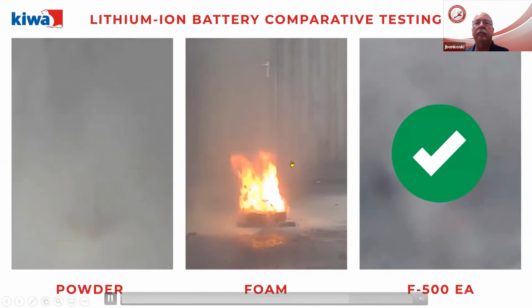These tests were done by Kiwa Labs on behalf of HCT Europe and Johnson Controls in trying to find an independent third-party solution for one of their clients. They had asked F500 to participate in the testing, and we agreed as long as they shared the results. So this is why you see Johnson Controls' name on this particular slide, because this comes right out of their literature where they're showing, based on the tests they did over the course of days, that powders were poor, not recommended, do not apply. Look at foam - well, Johnson Controls is a major foam manufacturer, so they really don't want to bash themselves too much, so they give it a moderate to poor, but in the remarks, not recommended to apply on a lithium-ion battery.